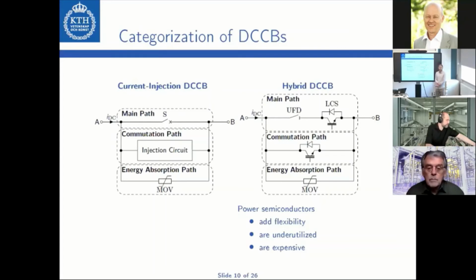Regarding this implementation of the making switch you questioned, one can of course see that here it is general - it could be any injection circuit, and it could, for instance, be a solution as Cybreak has used, which does not use a making switch, as far as I'm aware, rated for the full DC link voltage, but only for a fraction of the whole system voltage.